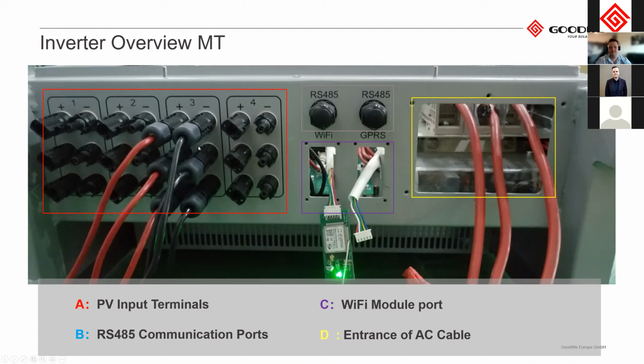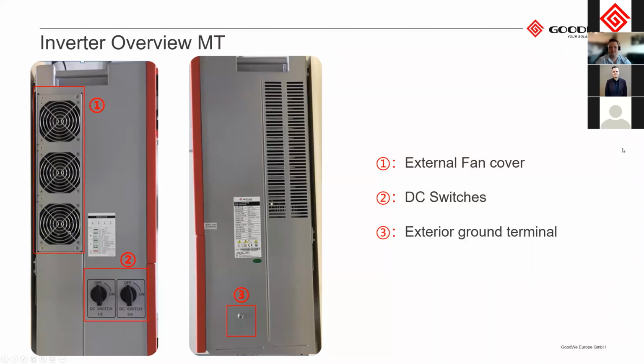You can see the MPPT inputs. This one specifically is most likely an 80 kilowatt MT. You'll see it has 3 inputs per MPPT on each of the 4 MPPTs. We then have our RS485 connections and then the Wi-Fi communication port for the Wi-Fi. Just a side view of the inverter as well.